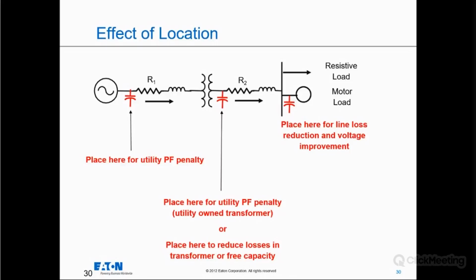If I walked into a plant and there were 2 or 3 large horsepower air compressor loads that contributed to the poor power factor, I would probably try to place them at the motor. If I walked into a facility like a distribution facility and there were hundreds of motors all over, by the time you went around and installed smaller kVAR capacitors at the motor loads, you would probably, from an economic standpoint, be better off to come outside the plant at the common point of coupling and install the power factor correction there. I will say that the smaller type fixed capacitors at the motors, that business has kind of been declining for a number of years.